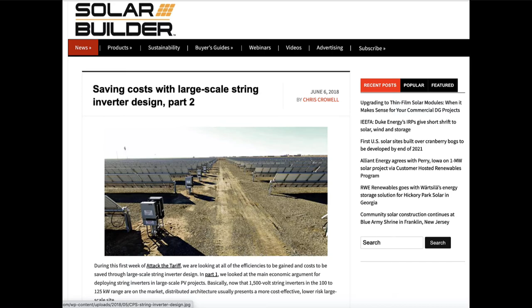The big problem on large scale PV over the last 10, 15 years is that there's only a couple companies still in existence over that time. Most companies selling products into that market have been in and out of it, some 2 or 3 times. So customer service for those large scale inverters is poor at best, extremely poor. There are plenty of plants where, as inverters start to fail, they're faced with having to physically remove the inverter or bring in another and set it next to an extremely large one because they can no longer get parts for it.